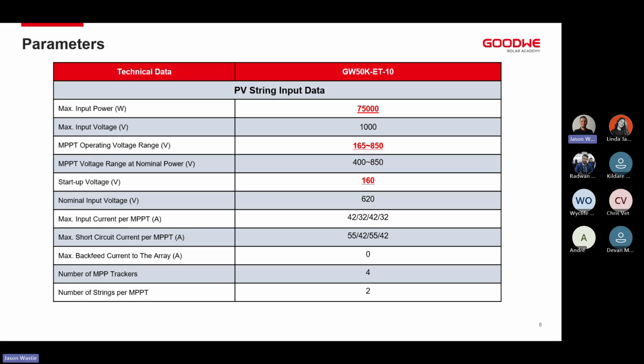So on the ET50 inverter, we can add 75 kilowatts of PV, or usable PV energy is what we can get through the inverter, meaning 75 kilowatts of PV is what we can load onto the inverter. 50 kilowatts of that can go towards your loads, 25 kilowatts of that can go towards your batteries at exactly the same time. In any iteration, so you can have 20 kilowatts of load and 50 kilowatts of PV charging towards your batteries to a maximum of 75 kilowatts. So it's 150% PV oversizing.